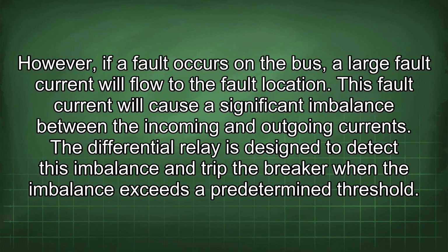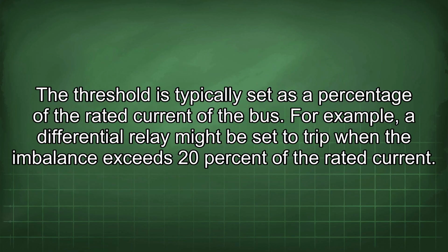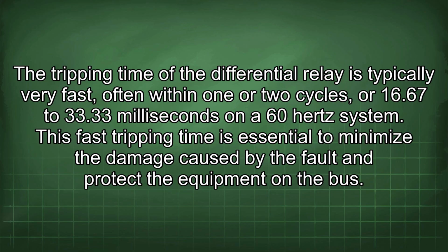However, if a fault occurs in the bus, a large fault current will flow to the fault location. This fault current will cause a significant imbalance between the incoming and outgoing currents. The differential relay is designed to detect this imbalance and trip the breaker when the imbalance exceeds a predetermined threshold. The threshold is typically set as a percentage of the rated current of the bus. For example, a differential relay might be set to trip when the imbalance exceeds 20% of the rated current. The tripping time of the differential relay is typically very fast, often within 1 or 2 cycles, or 16.67 to 33.33 milliseconds on a 60 Hz system.